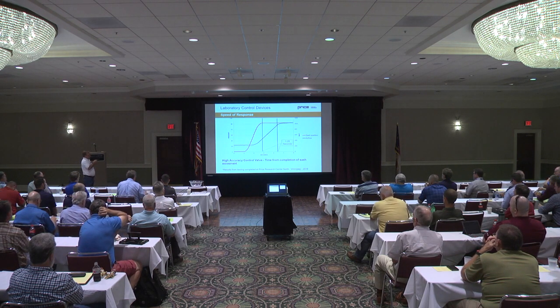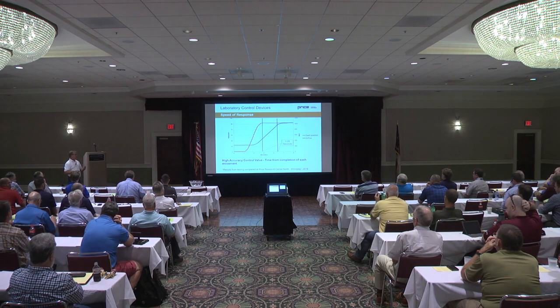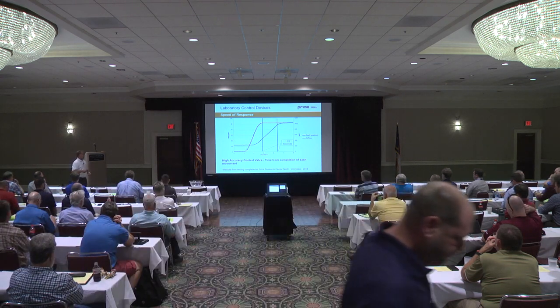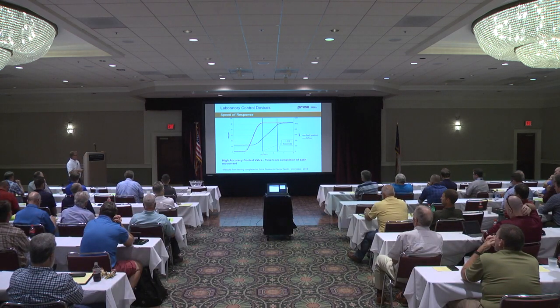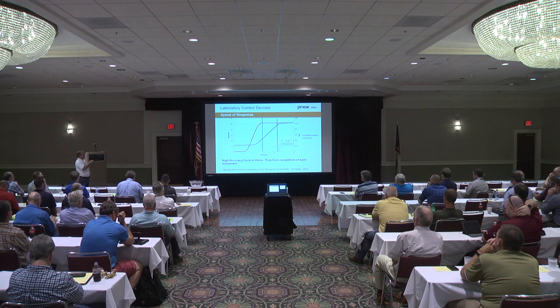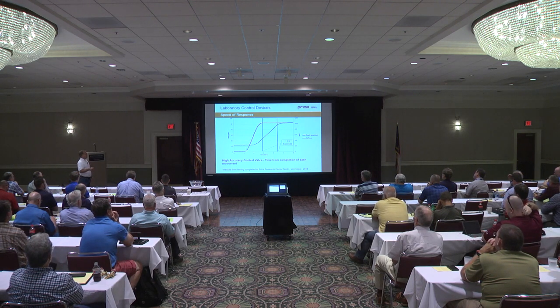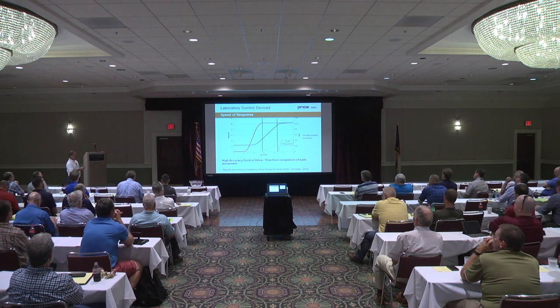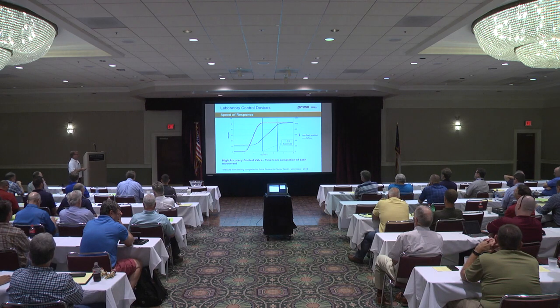So on the high accuracy control valve is where we're using velocity pressure to measure through a transducer. Vortex shedding would be a similar device, and thermal dispersion would be similar, where again, the same graphs go back to sash movement to airflow. Reaching airflow is 1.25 seconds. The Venturi valve was 0.8. Again, the documents state less than 3 seconds. So it still does very good control of getting the fume hood to its control point.